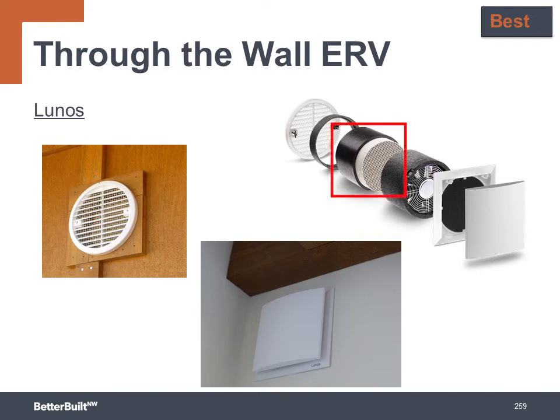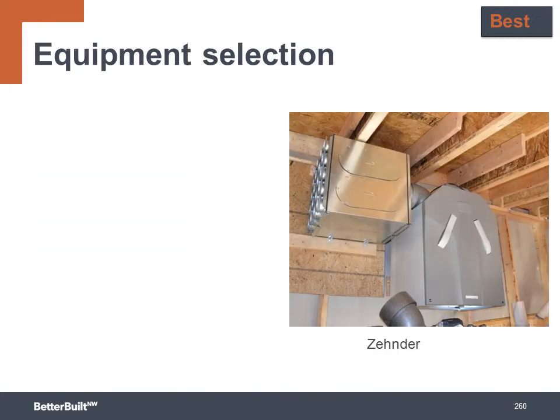As the air flows through the ceramic heat exchanger, the heat is captured in the core of the fan that's working as the exhaust fan, and then the heat is released into the fresh air stream when that fan becomes the supply fan. It takes advantage of the basic principle of heat moves from warm to cold. So when choosing the right ventilation system for your project, you'll want to think about these considerations. Efficiency of motors and efficiency of heat recovery if you're going with a HRV or ERV.